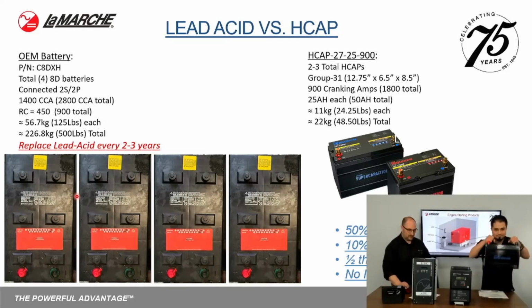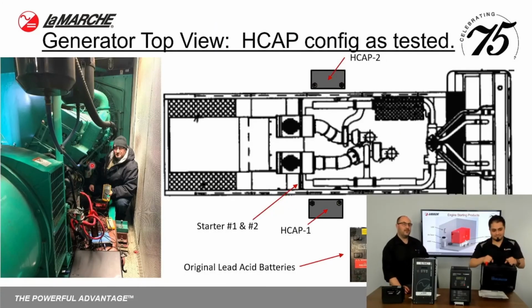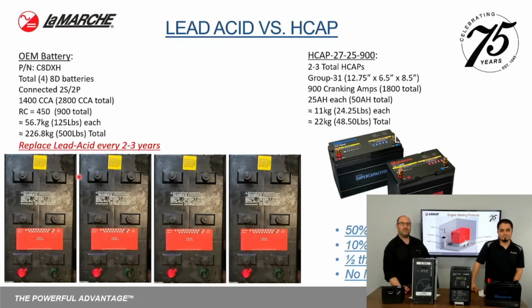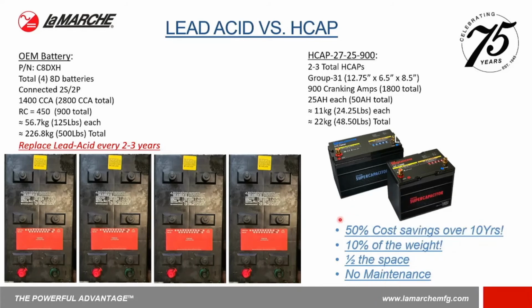And as you can see in the previous picture, there's not a lot of room for 2 guys to fit in here and actually replace batteries. So it's very easy for one technician to install these. When looking at the total cost of ownership, you'll have easily at least a 50% cost savings over the life of the product, only 10% of the weight, less than half the space, and 0 maintenance as compared to a lead acid battery.